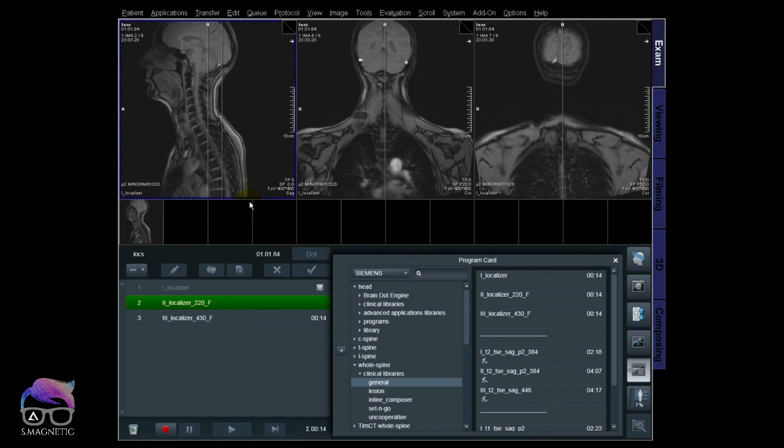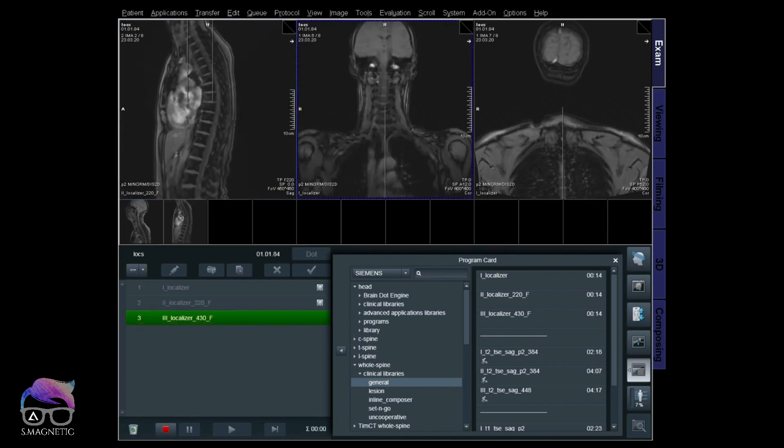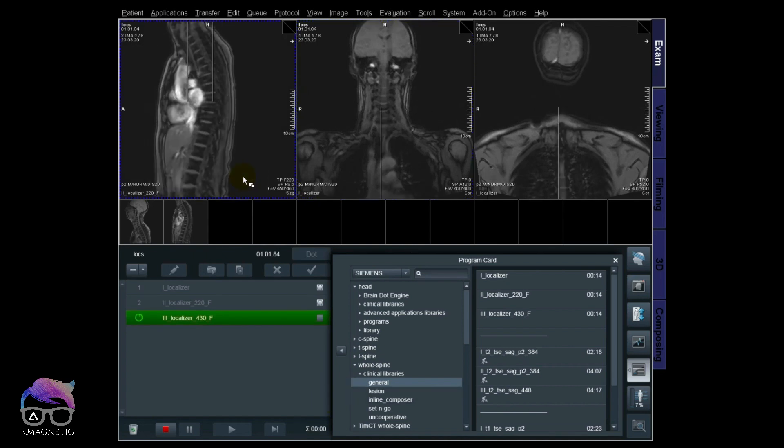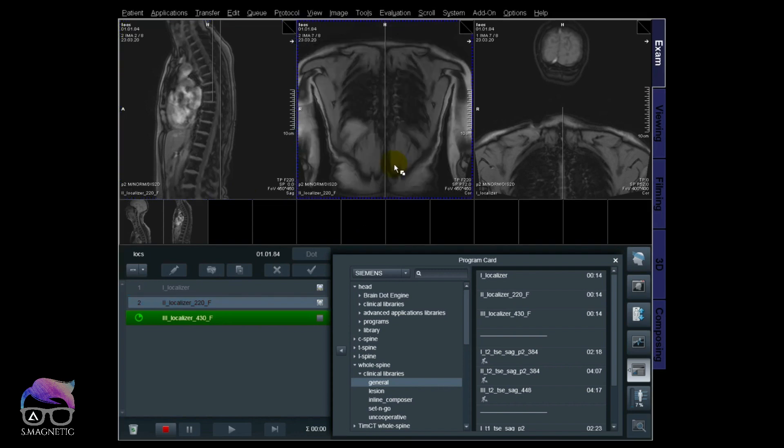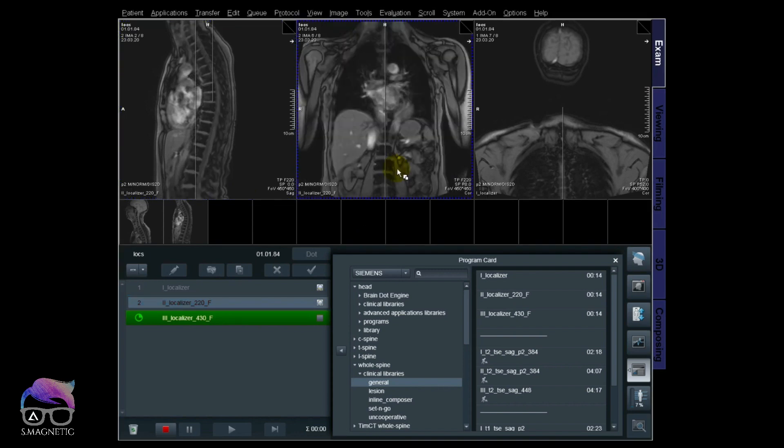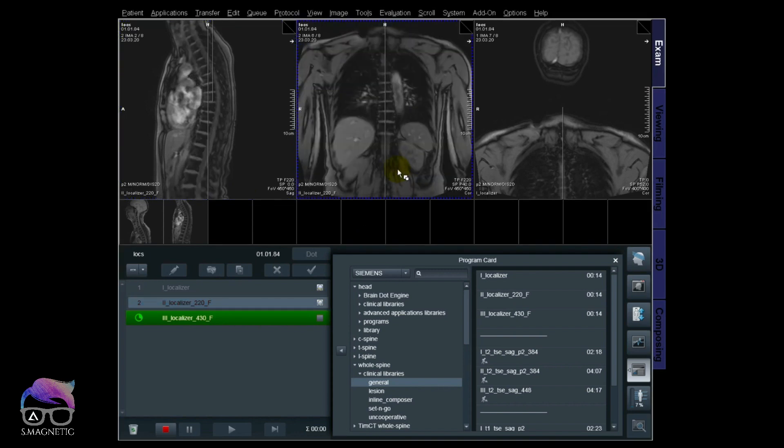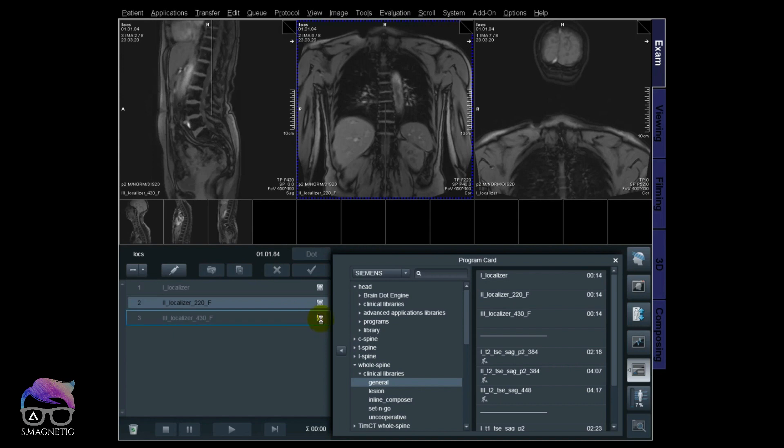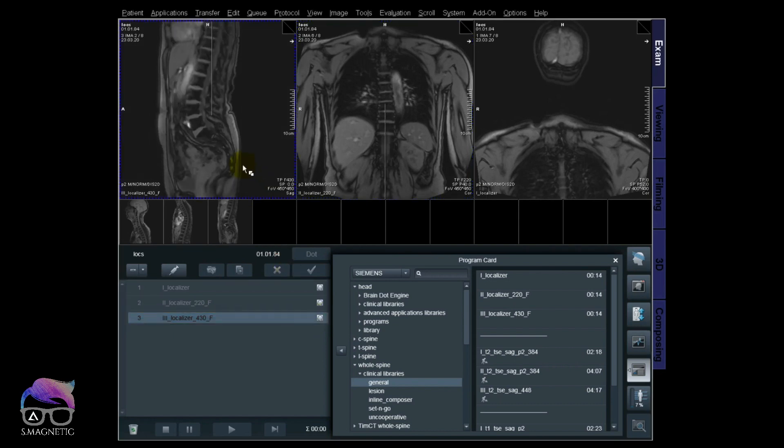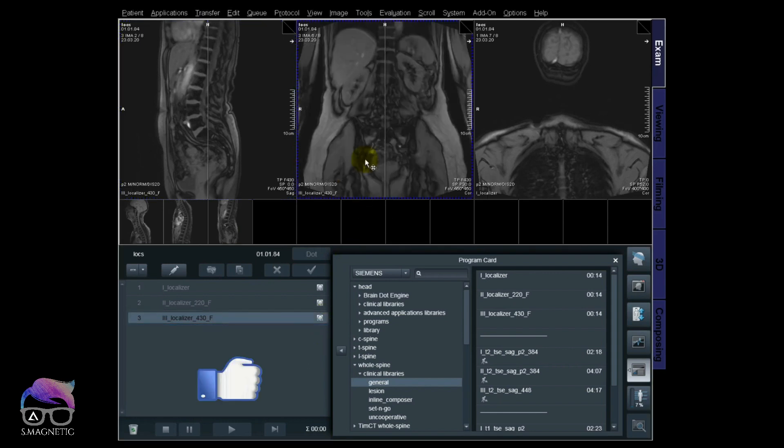Let's go live at the scanner. We are using 1.5T Siemens for this test on a healthy volunteer. I'm just gonna show you different areas where you can do improvement on the localizers. I'm just gonna show you a few areas. Let's go for the whole spine and I just pick here three sequences directly from a Siemens tree and these localizers are three steps. So it's 14 seconds times 3 covering the whole spine.